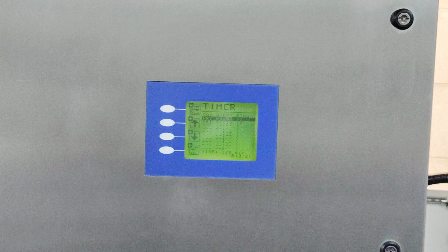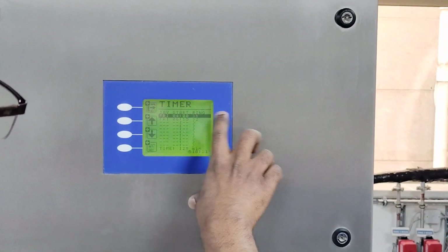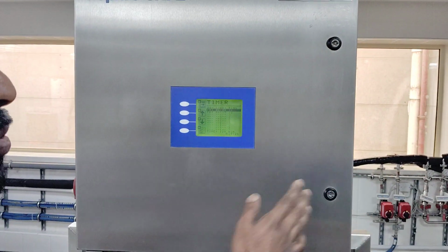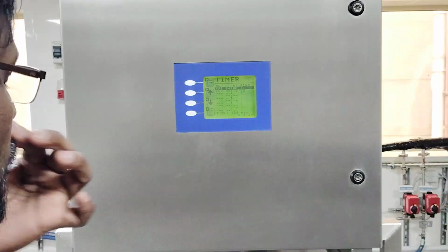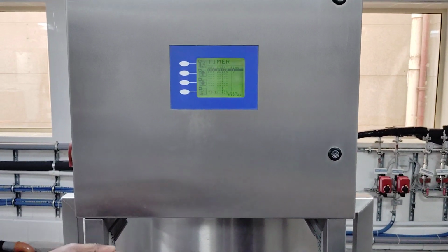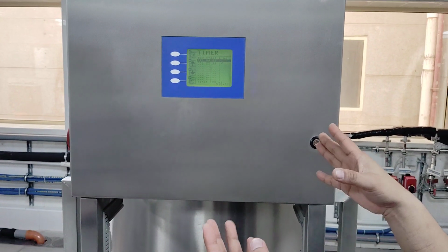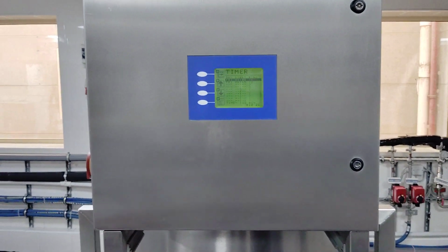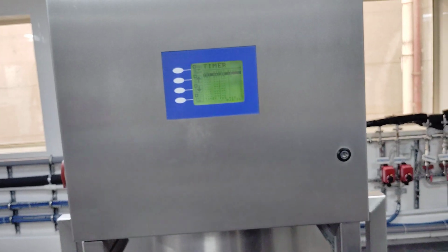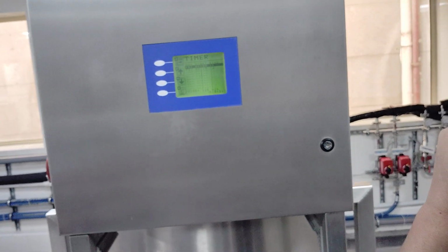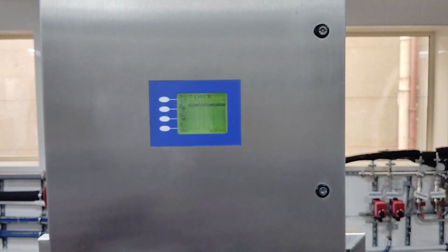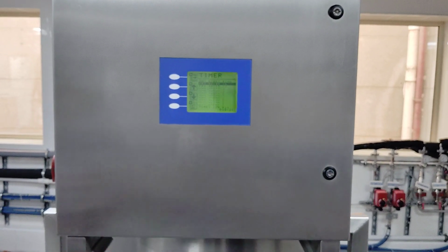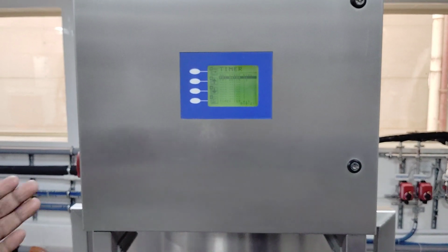So every Friday we are doing this, these two loops are there. One loop will start at 4 o'clock. After it finishes, the second loop will start at 6 o'clock. Automatic hot cleaning. During this time, we cannot use the dialysis. That's why we are doing it on Friday. They already know that every Friday is scheduled. But once the heat distribution has started, we can terminate it. Yes, we can terminate, but it will take 10 to 15 minutes to cool down completely. It will consider that the heat distribution has started.